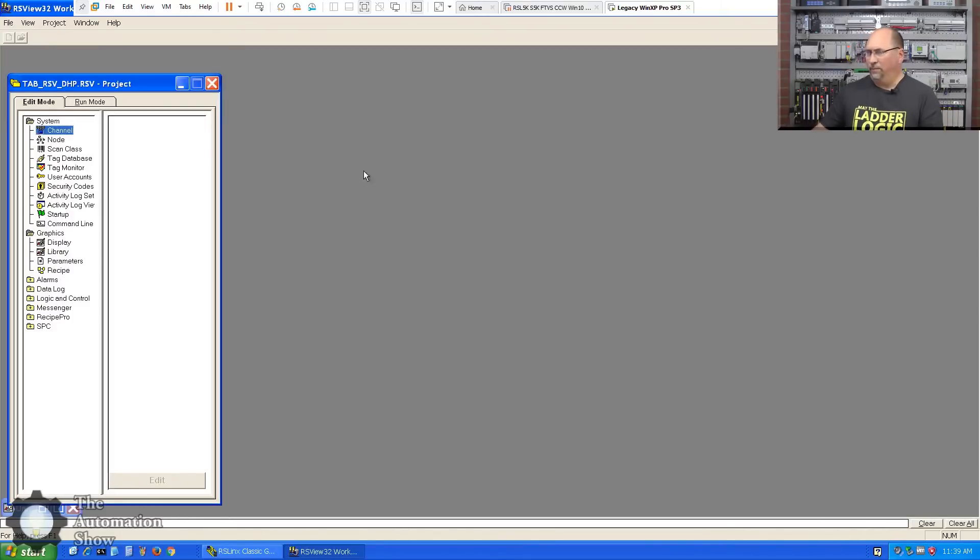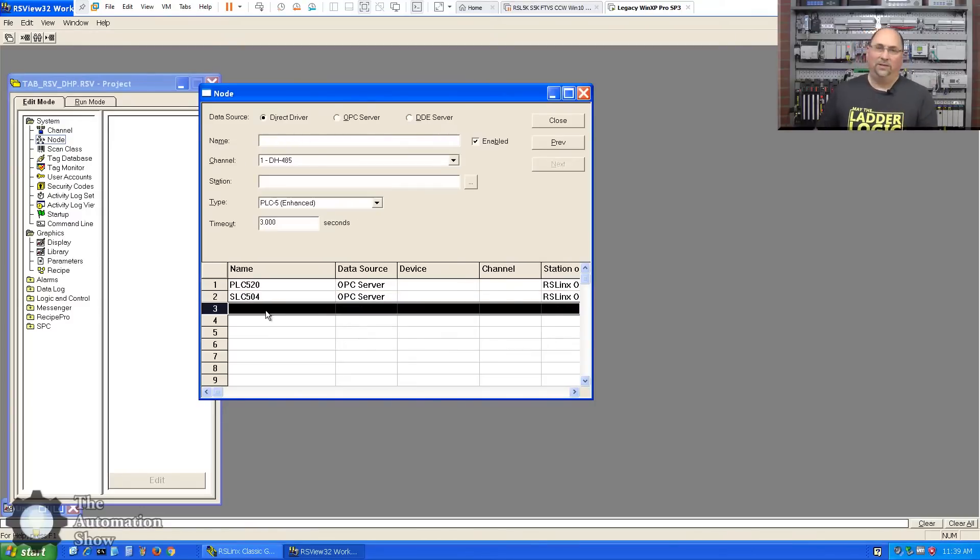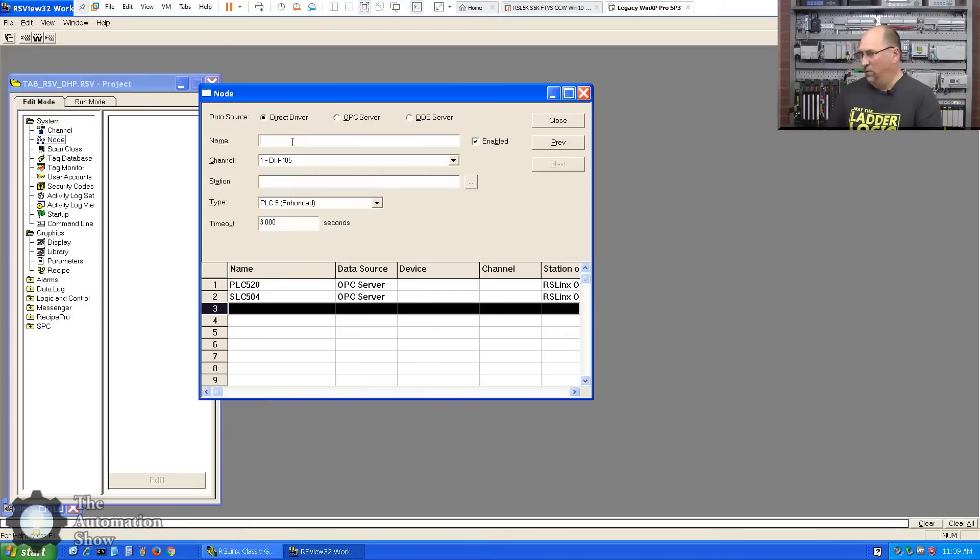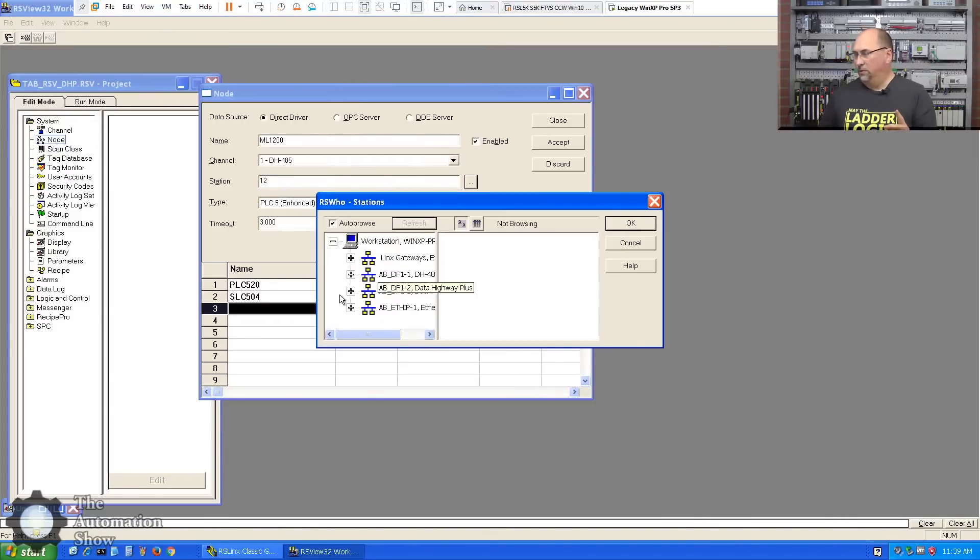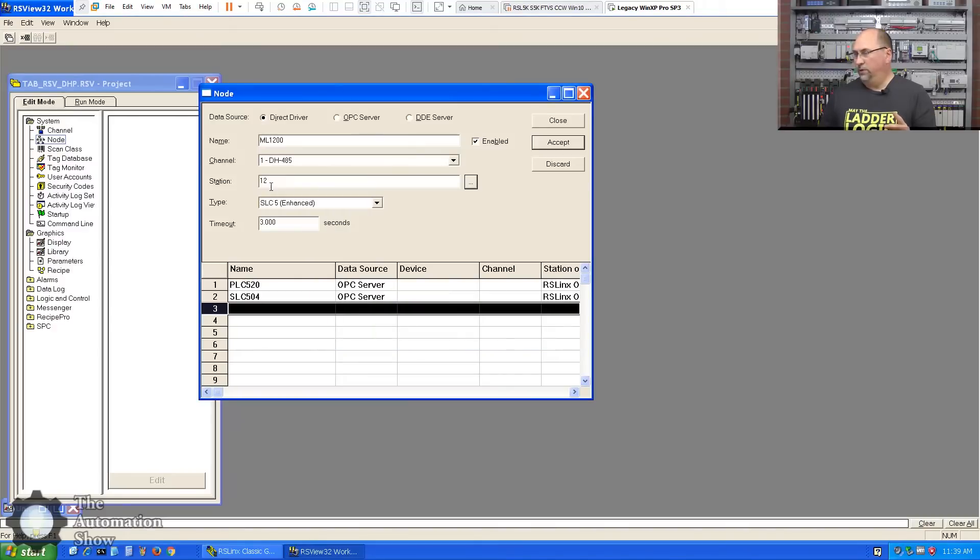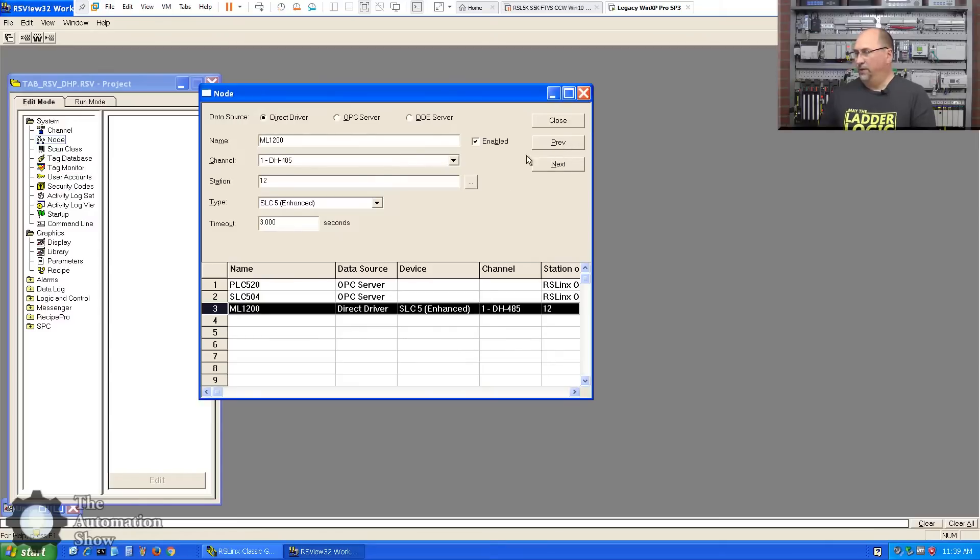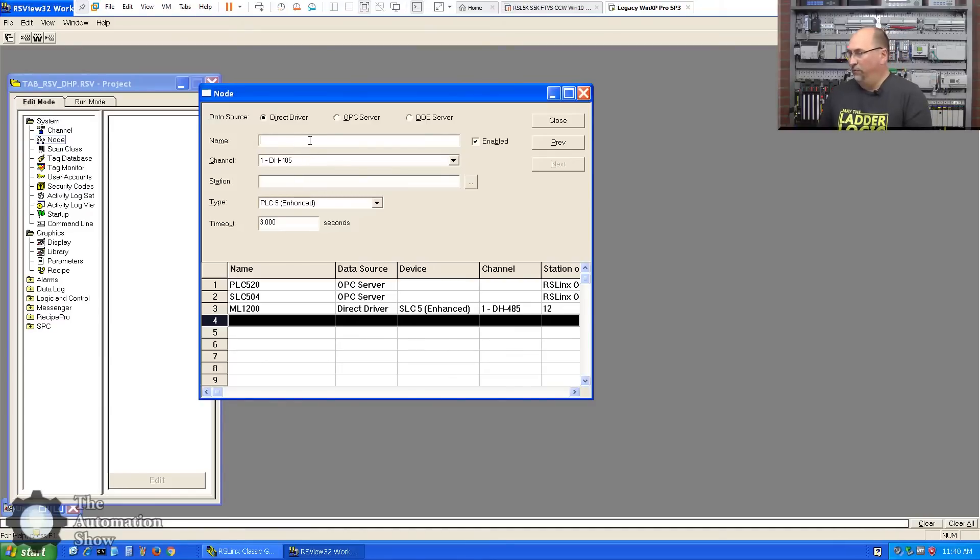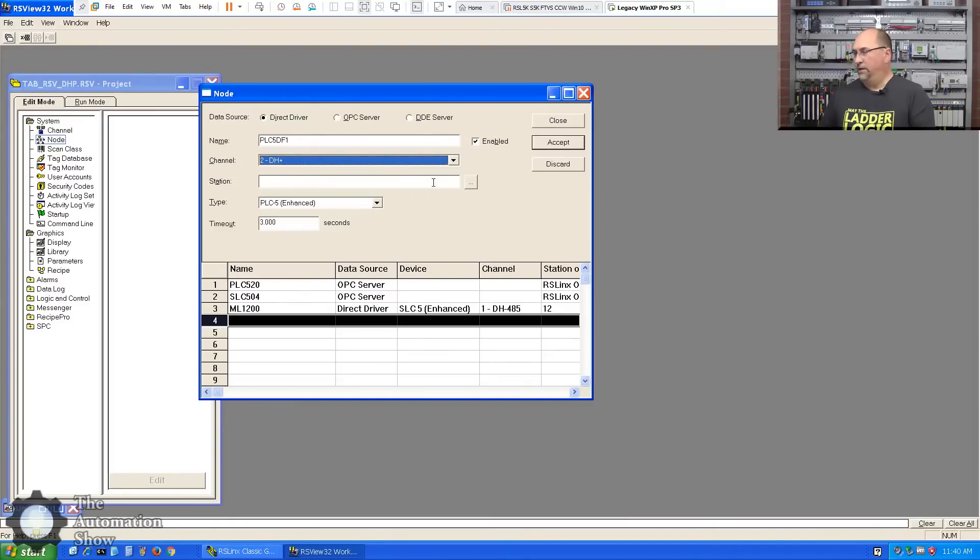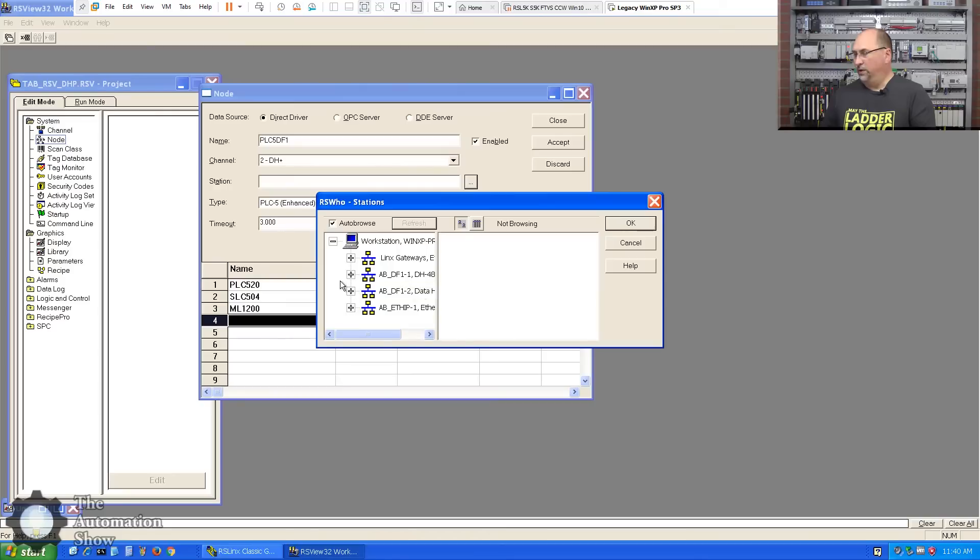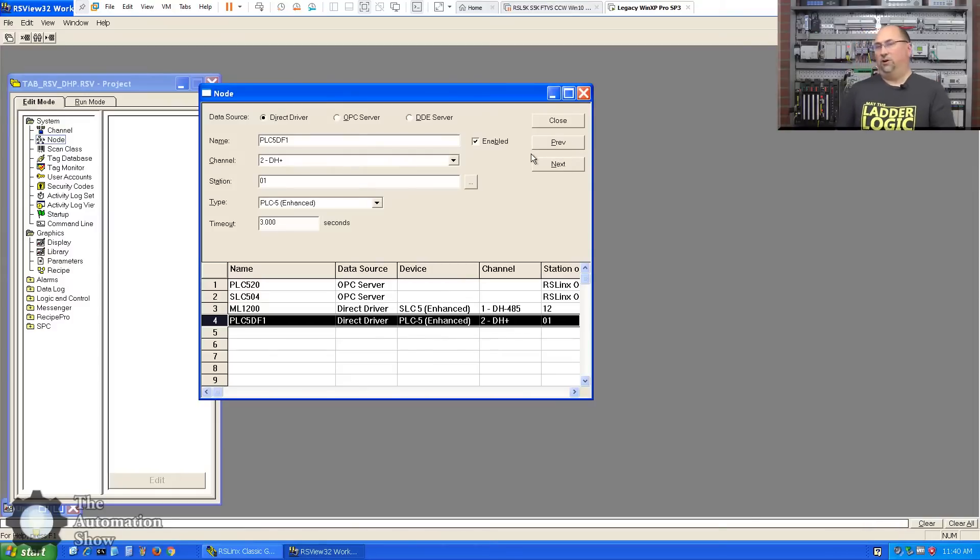And I'll click over here on three and so those are now set up. So that was a little tricky, but in any case we'll click on okay here. And now we have to add our nodes. I'm not going to add everything that's on the DH485 just for the sake of time. So let's just add the 1200. We'll call it ML1200, direct driver DH485, that's the first one. Station number is 12. Now we could browse for that here. Let's see here, 12, okay good. I'm just going to leave that the way it is, that sounds good, so we'll accept that.